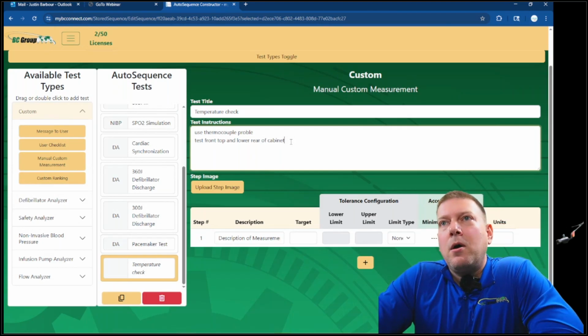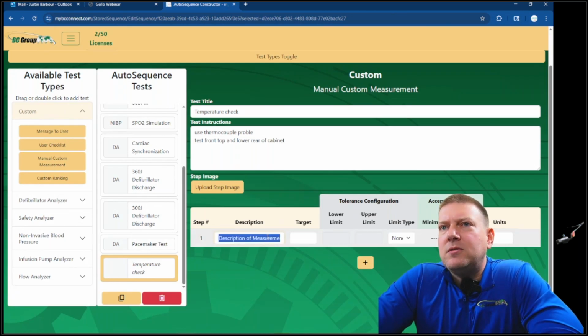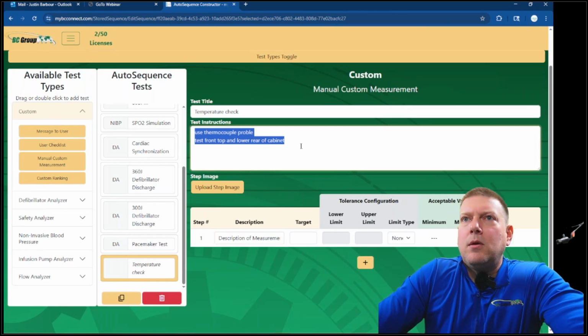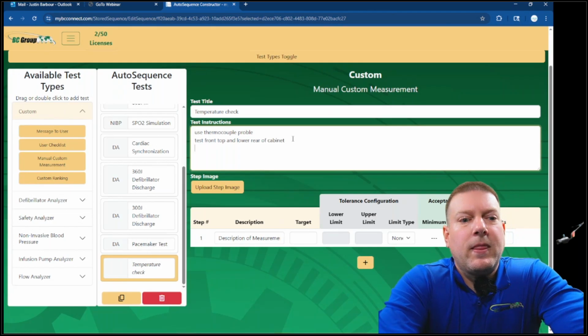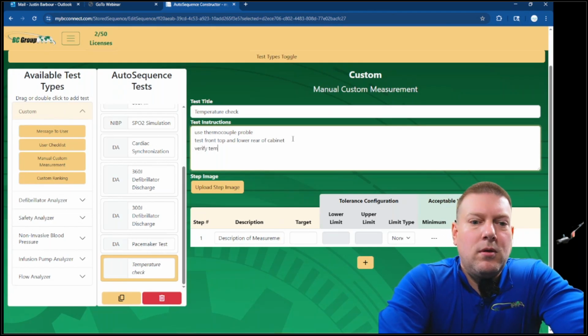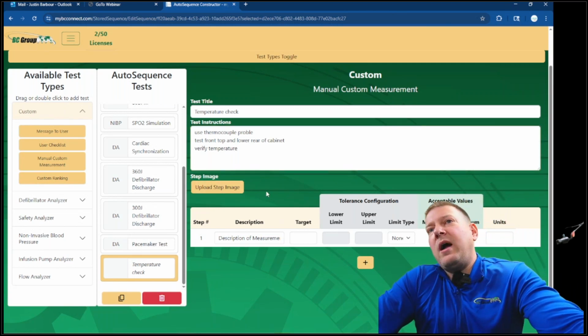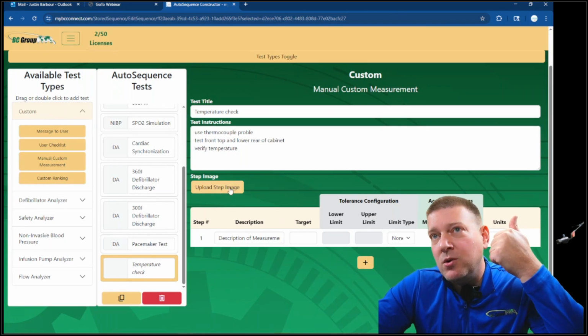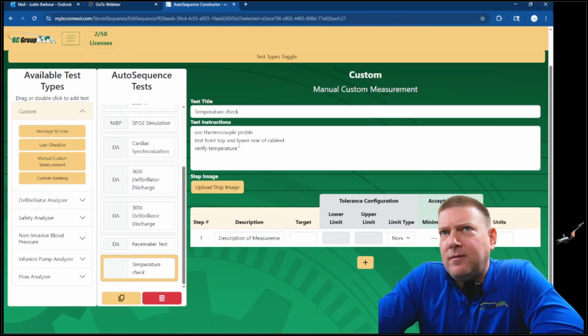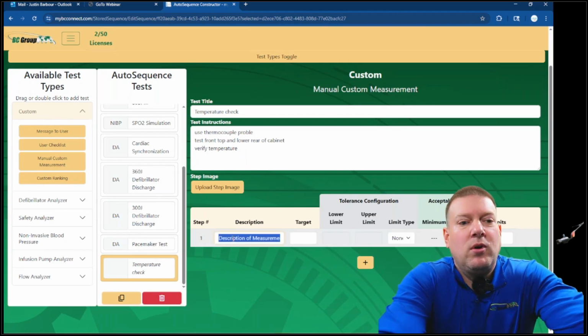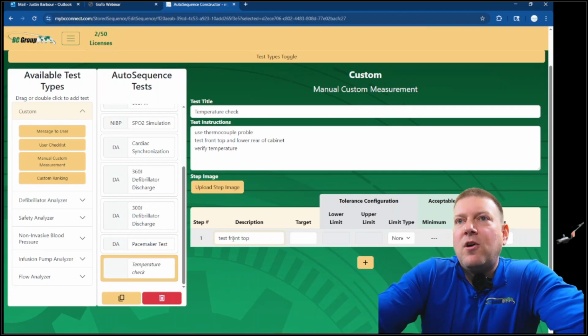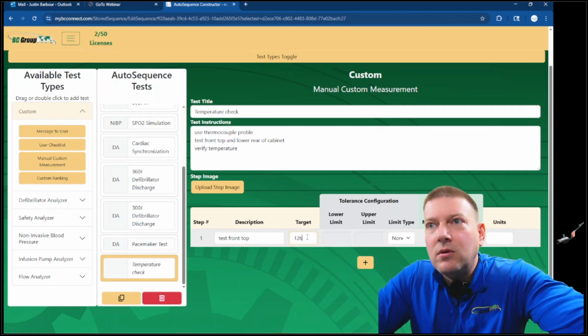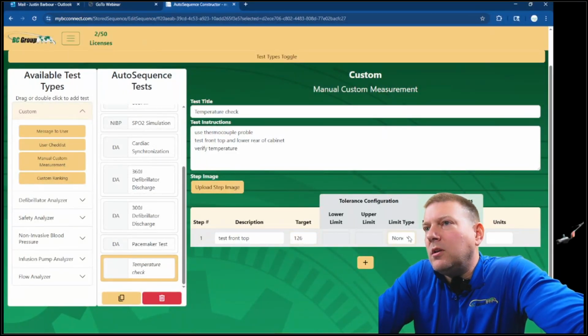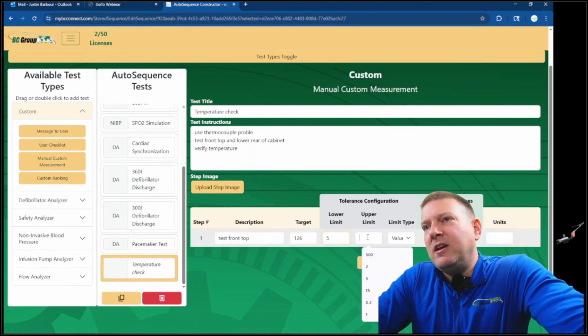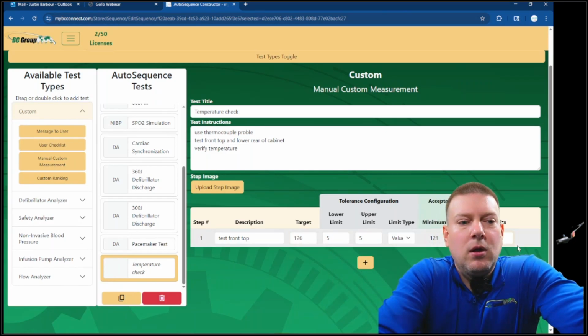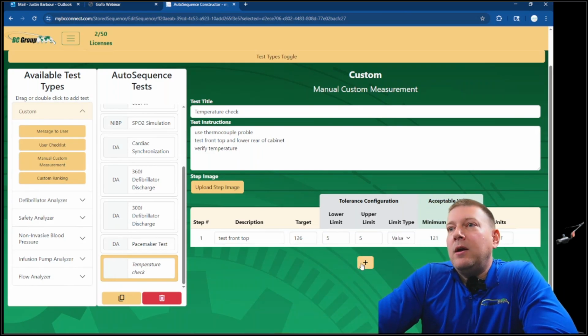Okay, so I've given them instructions on what I want, and now let's add 2 different measurements. Okay, come on, there we go. Verify temperature. Okay, here is where I would incorporate step image, either of the thermocouple probe I want them to use, or where in the cabinet I want them to test. I think my description was pretty accurate, test front, top, and lower rear. And here we're going to do front top. We're looking for 126 degrees. 126, limit type, value. And let's say 5 degrees above and below 126 degrees Fahrenheit.